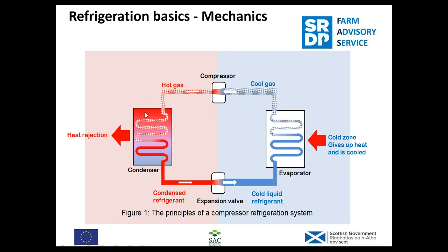The high-pressure hot gas goes into the condenser — usually sitting outside the refrigeration plant, or in a fridge it's the tubing on the back. The refrigerant gas can be at anywhere between 40 and 120 degrees depending on usage. It gives off heat and as it does so it condenses back to a liquid. Still at high pressure, it then goes through the expansion valve, which as it expands loses temperature and drops pressure. It's gone from a high-pressure liquid to a low-pressure liquid, becomes very cold, and starts to absorb heat. So that's the cycle.